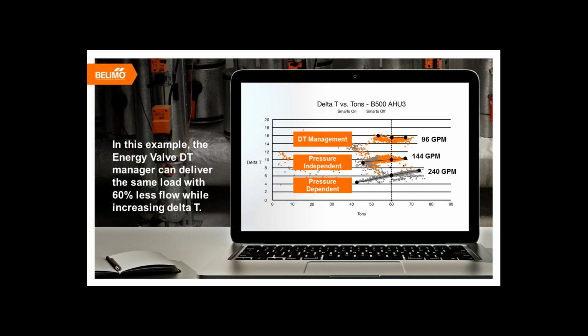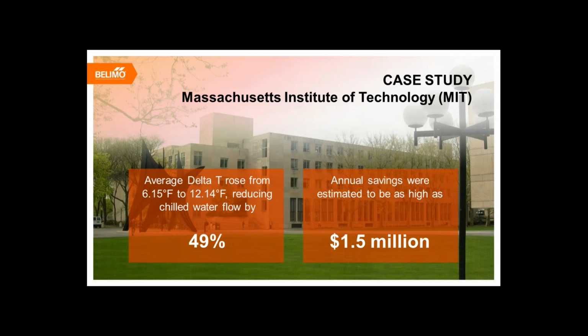So these are a couple examples, but now I'll show you a couple great case studies that we've done with Energy Valves. The first case study was at the Massachusetts Institute of Technology. This was one of our first Energy Valve customers and one of our biggest success stories to date.